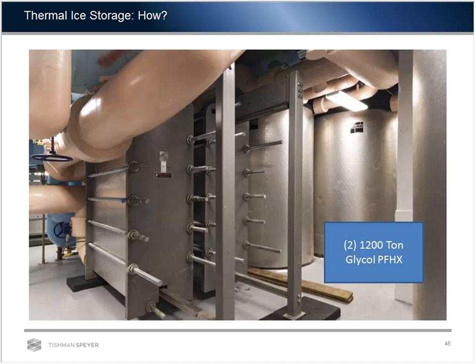Some of the plate and frame heat exchangers, as you see here, have glycol going in one side — our antifreeze from the tanks — exchanging with chilled water on the other side. We have two of these glycol plate and frame heat exchangers at 1,200 tons each, giving us 2,400 tons of cooling capacity from the tanks at our disposal.